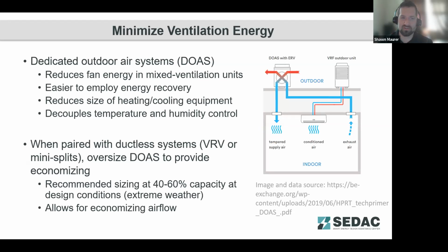Dedicated outdoor air systems are also a great way to minimize ventilation energy because they bring all your ventilation air, your exhaust air, to a common place where you can now put a heat exchanger on that and recover energy from your exhaust air and put it back into your ventilation air going into the building. It's also going to reduce that fan energy for ventilation, where if you've got mixed air coming to the unit as well as outdoor air for ventilation, the fan must be sized significantly larger to handle both those airflows.